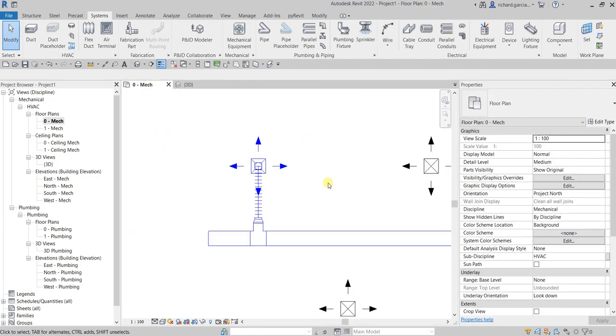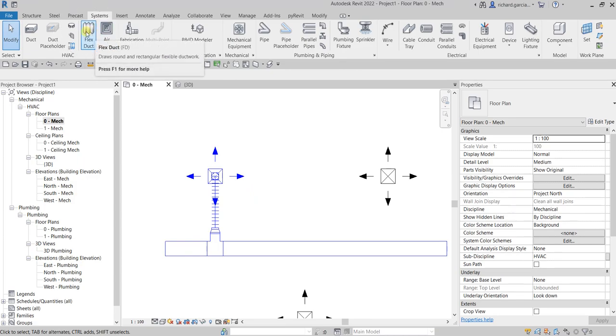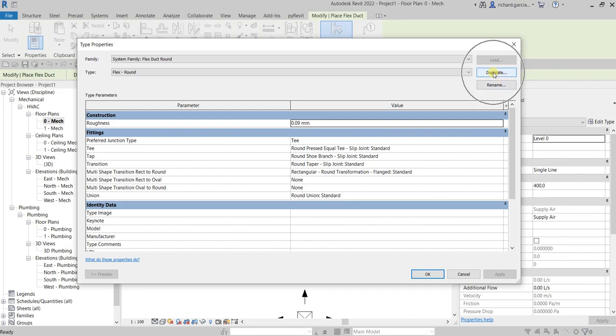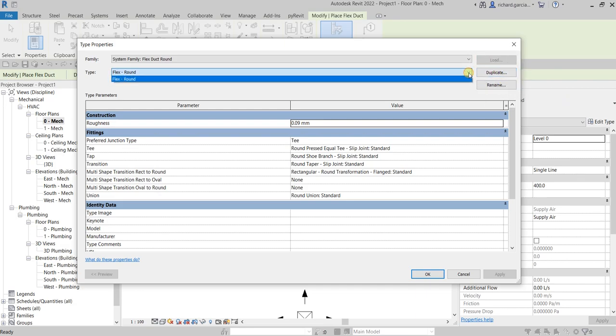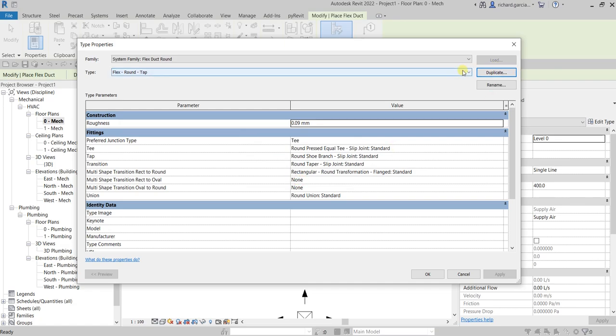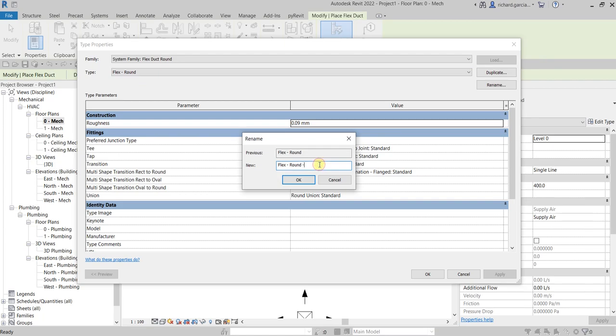To do that, go back to the floor plan and create a flex duct — the shortcut is FD. Before you pick any connection, go first to the Type Properties, because we are going to create a new type of flexible round. Let's duplicate this and change the type name to 'Tap'.